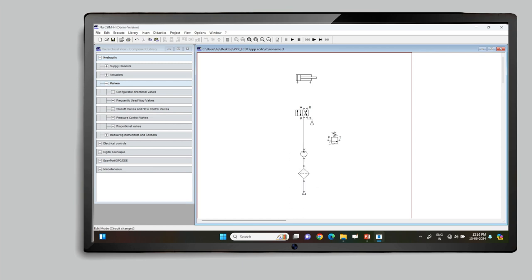The pressure relief valve, which safeguards the system, has its input side connected to the pressure line and its output side connected to the reservoir. The two points available on the direction control valve are connected with the two points on the double acting cylinder — one is the piston side and the second is the rod end side.